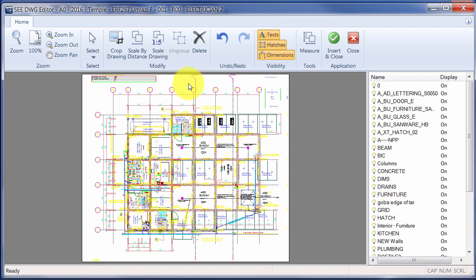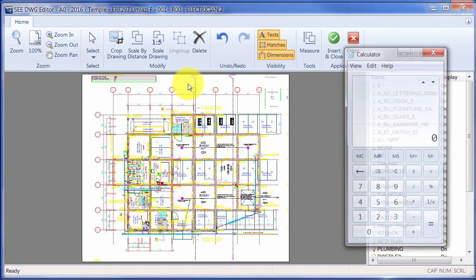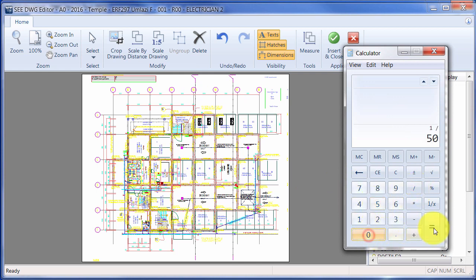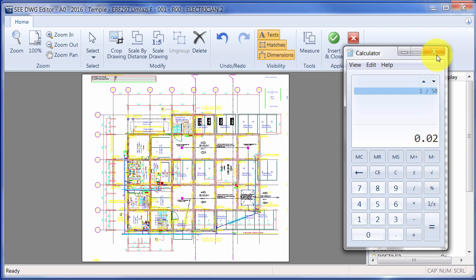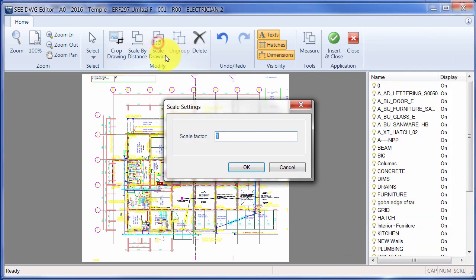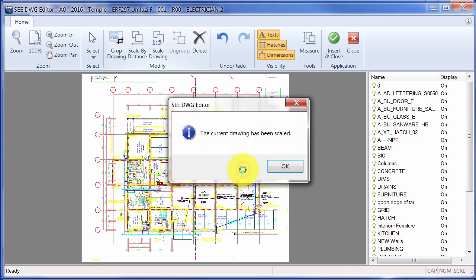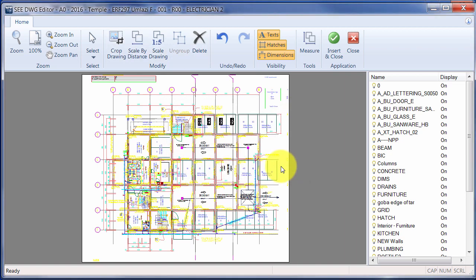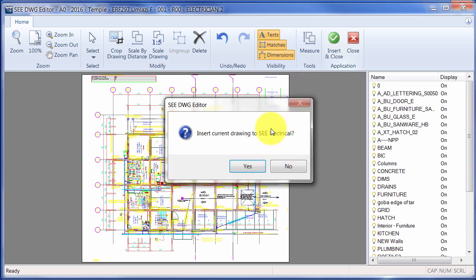So at the moment it's 1 to 50. So if I choose a calculator, just do a quick calculation: current scale over the scale of the page I'm bringing it into. So it's 0.02. So I'm going to scale the drawing by 0.02. Click on OK and I'm going to choose Insert and Close.